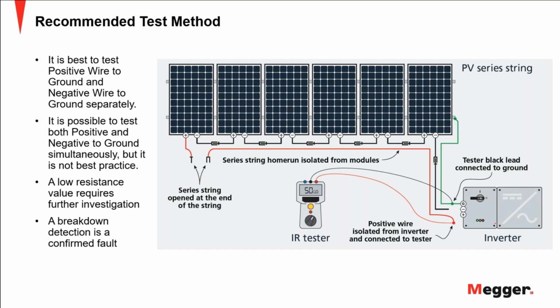And some manufacturers recommend doing the test under short circuit. So you short circuit this end here, and then you run the test. This is also connected here, and you run the test in a short circuit connection. It depends on what system you are testing. But no matter how you run the test, the result should be higher than 1 mega ohm. Below that, it's considered a fault and should be investigated.